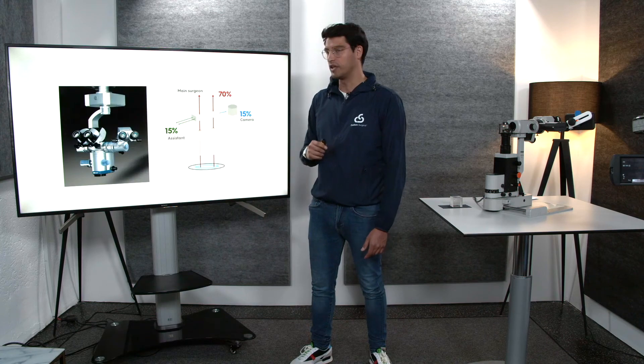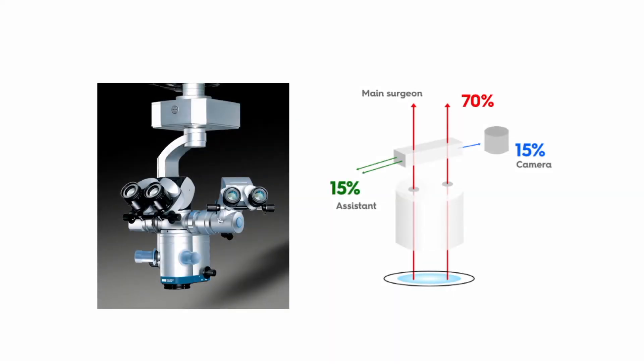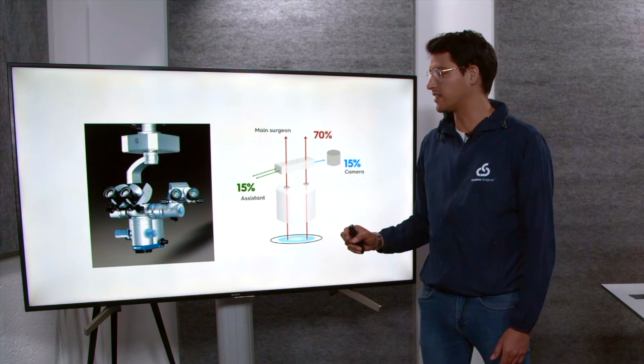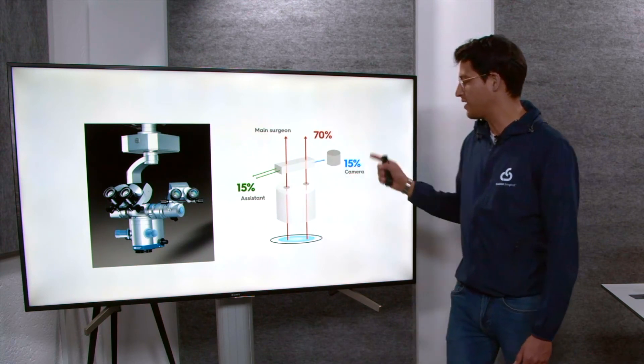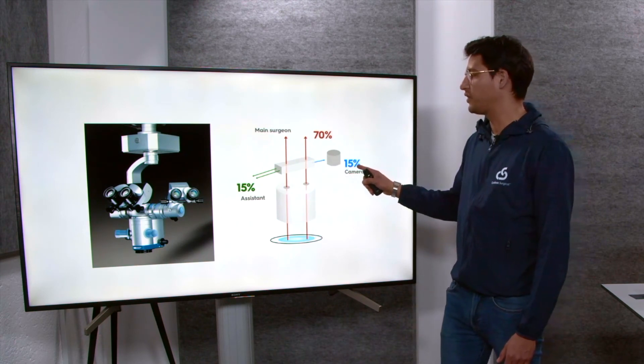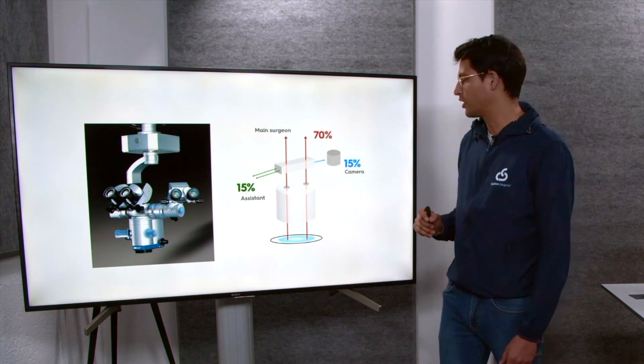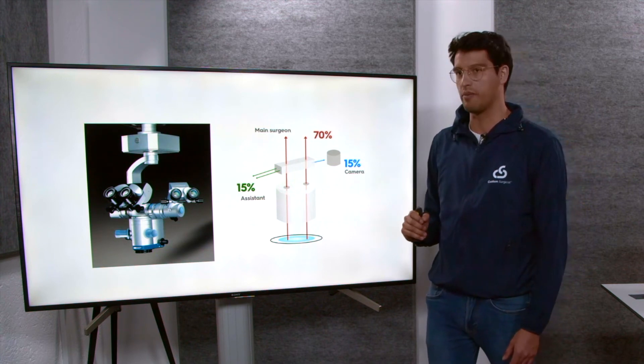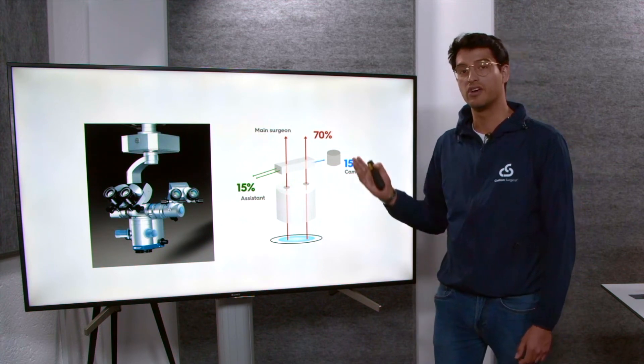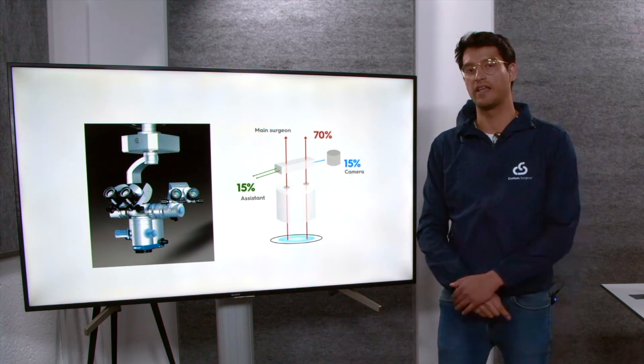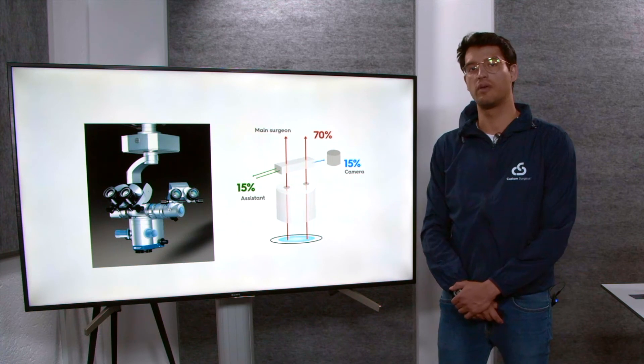On this third example, you will see that the beam splitter is used for two purposes. Initially, part of the light goes towards the assistant binoculars, and then another 15% of the light is going to the microscope camera. These are the applications that you can find when using beam splitters in medical grade microscopes.